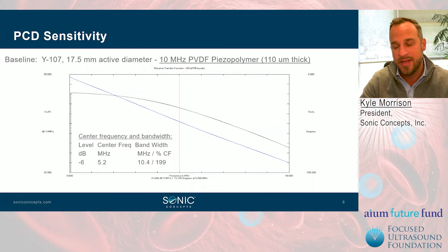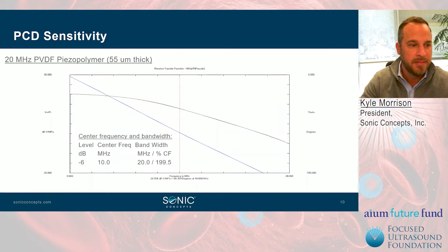So this is 110 micron thick piezopolymer material that we're using here. So look what happens when we go out to 20 megahertz. So it starts to fall off pretty rapidly using 110. So it worked up until 10 megahertz, but it falls off too much out to 20. So what we do is we reduce the thickness of that piezopolymer by half to 55. You lose about 6 dB or half amplitude but the bandwidth is there, so within 6 dB.